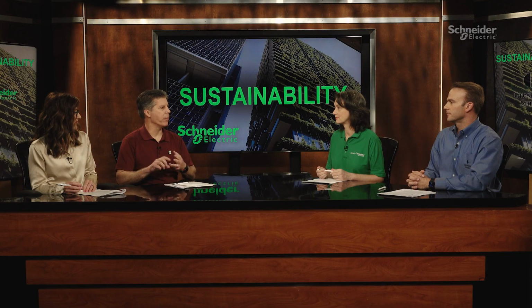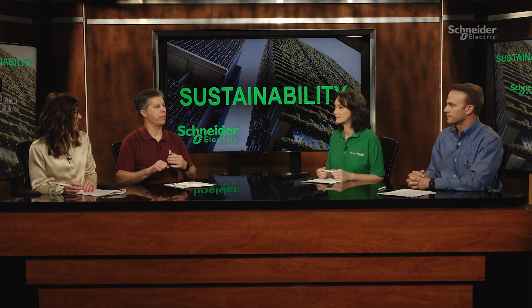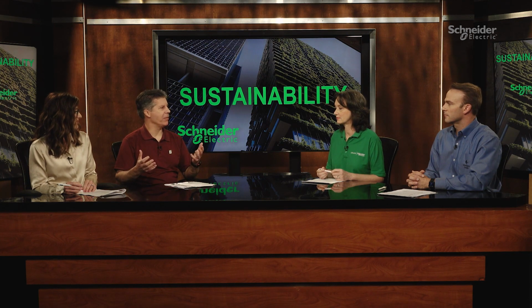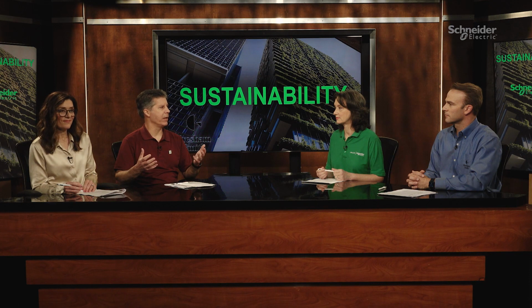So where is it required? Well, we have requirements for elevators in Article 620, and we have requirements for critical operations data centers in 645, and emergency systems, legally required standby systems, and so forth. So there are lots of places across the code where this gets pulled in. Let's look at a graphic that'll help us with understanding how this change in 240.11 will impact specifiers.